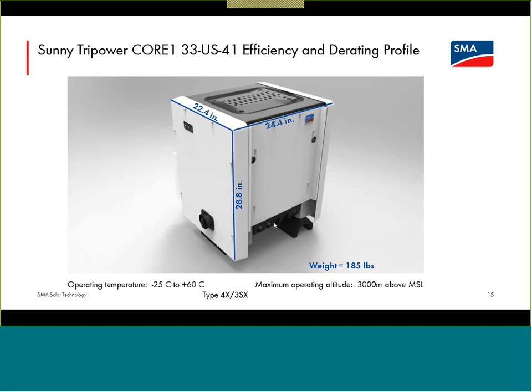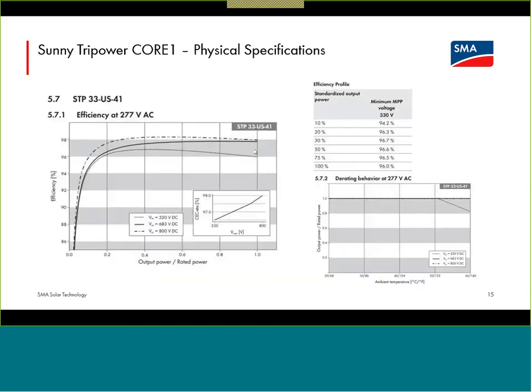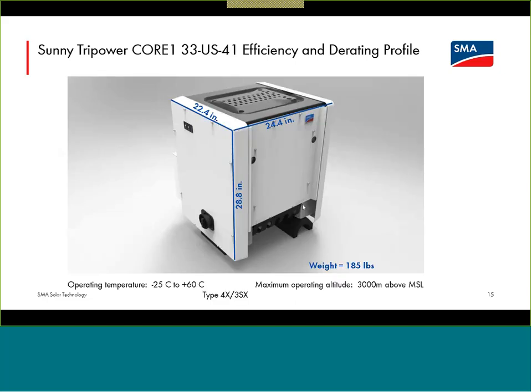And again, if that airflow path is impacted, then you're just reducing the ability of all of the built-in systems to cool the unit. So that's what we're saying, is that these derating starts would creep in at lower and lower temperature if this airflow path is impeded.